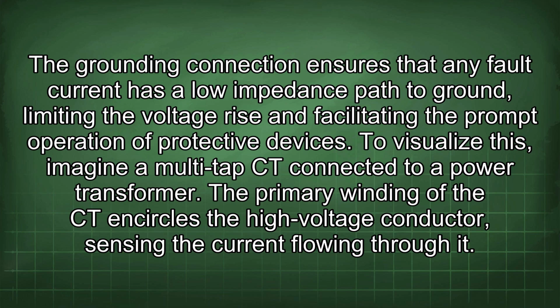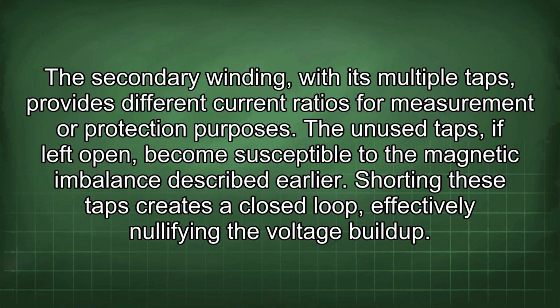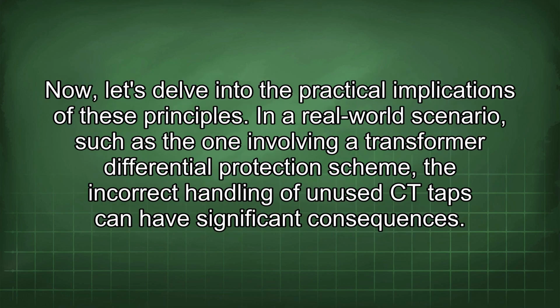To visualize this, imagine a multi-tap CT connected to a power transformer. The primary winding of the CT encircles the high voltage conductor, sensing the current flowing through it. The secondary winding, with its multiple taps, provides different current ratios for measurement or protection purposes. The unused taps, if left open, become susceptible to the magnetic imbalance described earlier. Shorting these taps creates a closed loop, effectively nullifying the voltage buildup. Now let's delve into the practical implications of these principles.